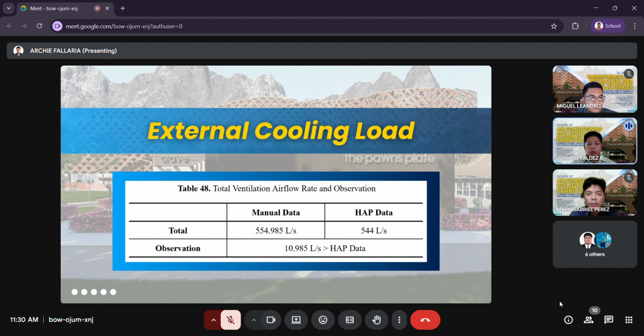Next, for the ventilation load. The table represents the ventilation load, which refers to the cooling demand associated with introducing fresh outdoor air into the indoor environment to maintain indoor air quality. As required by ASHRAE Standard 62.1, this load is especially important in a restaurant setting where high occupancy and food preparation activities can degrade the air quality without adequate ventilation. The manual calculation yielded a total ventilation airflow rate of 554.96 liters per second, while the HAP software produced a slightly lower total ventilation load of 544 liters per second, with a 10.98 liters per second difference.